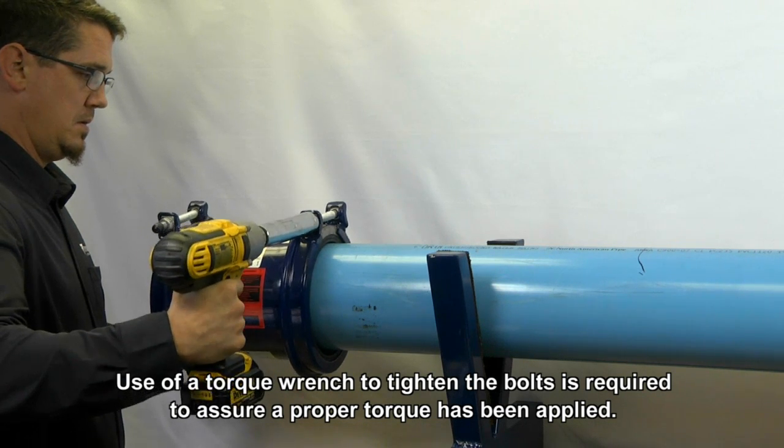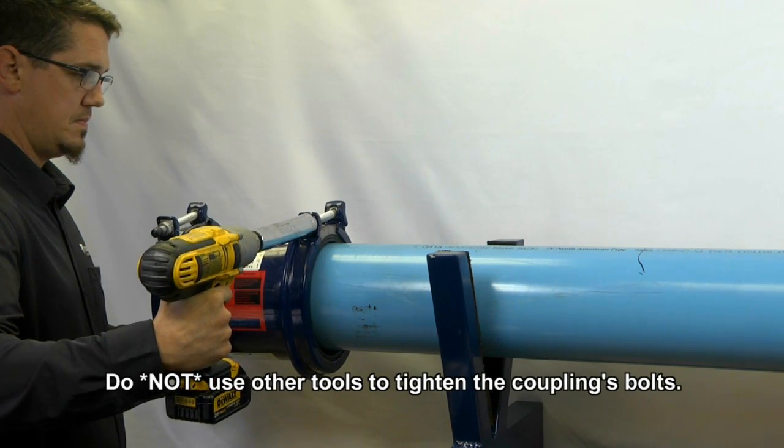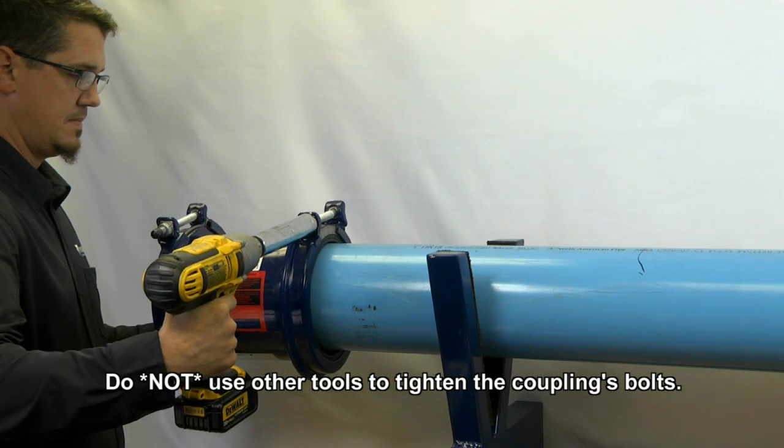Recharge the line and check for leaks. If any leaks appear, reduce the pressure in the line and increase the torque on the bolts by 50%.